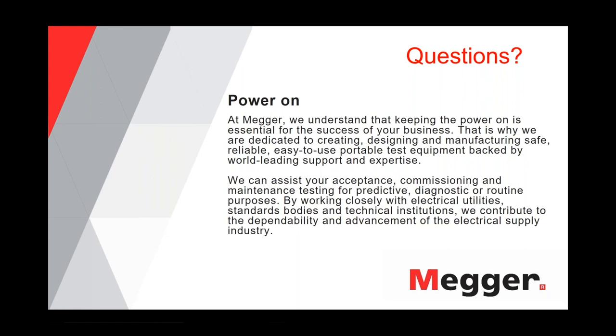All right. While we have you, why does rain affect TD results if the water is not entering the cable? Does water or weather conditions affect measurements of underground cables and conduits? Well, there are two questions in one here, right? One is basically how rain affects it. And rain can only affect an underground cable wherever you have a termination.